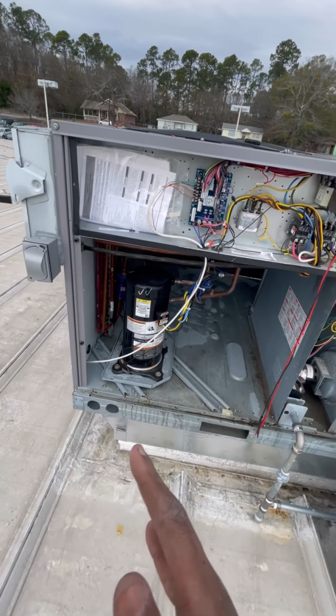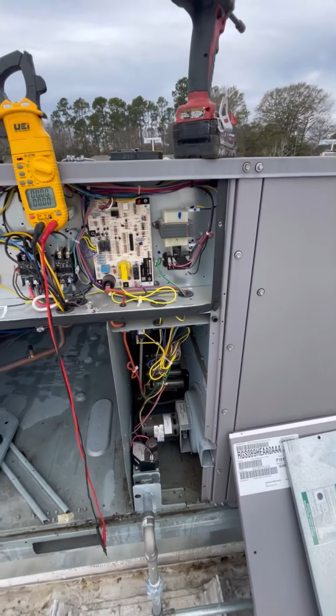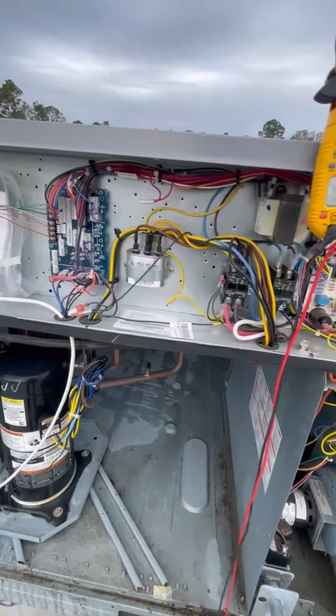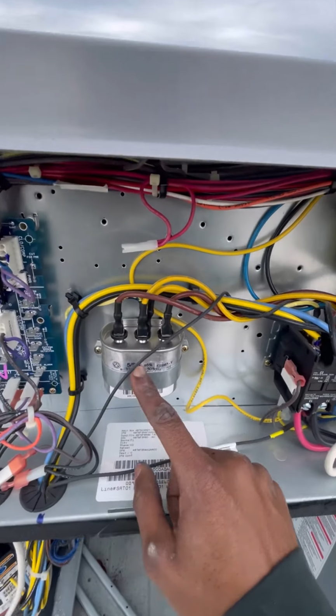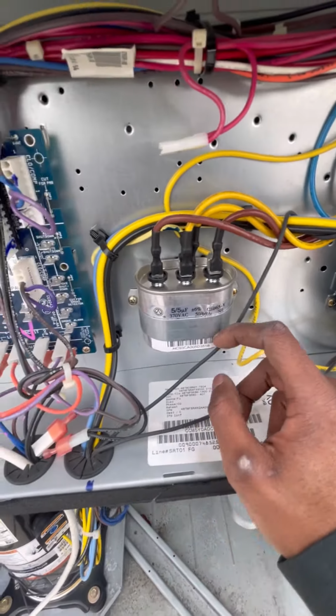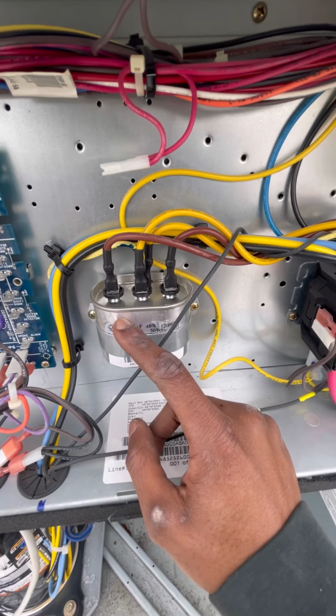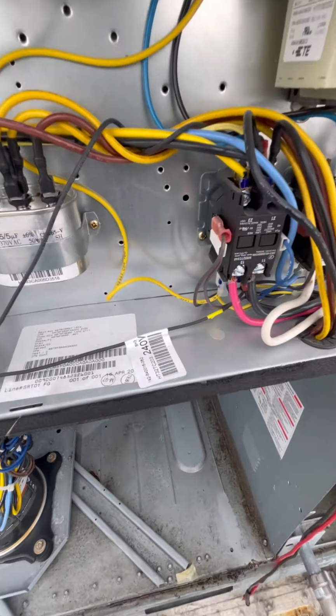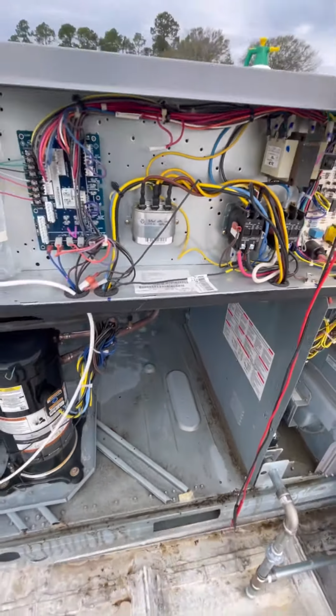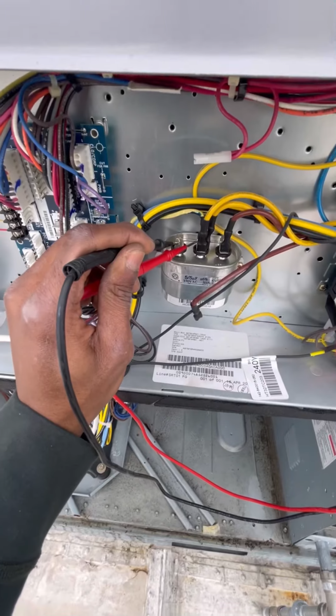So I pulled the electrical panel off. I only see 1 capacitor here, so that's gonna be the one we're gonna test out, right here. It's gonna be a 5/5, so 5 on the Herm side, 5 on the fan side. We'll test that out and see how that is looking.